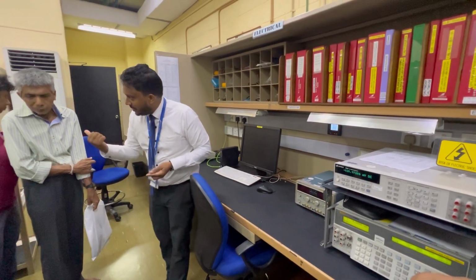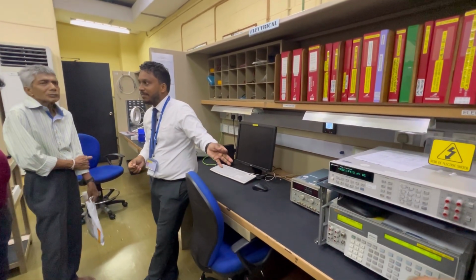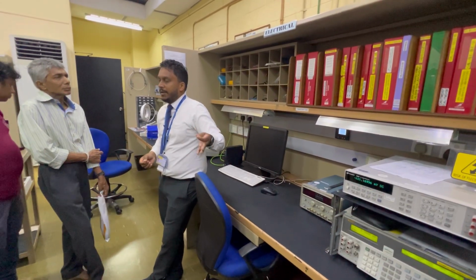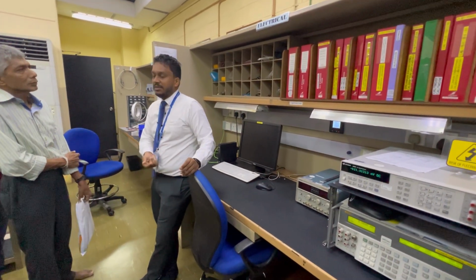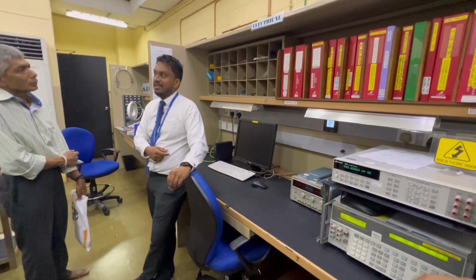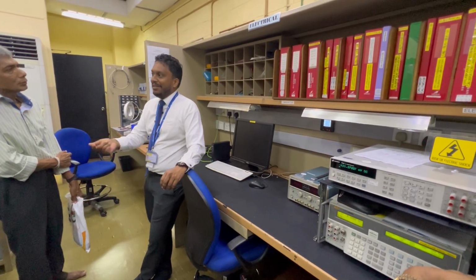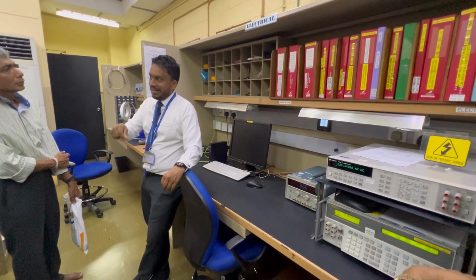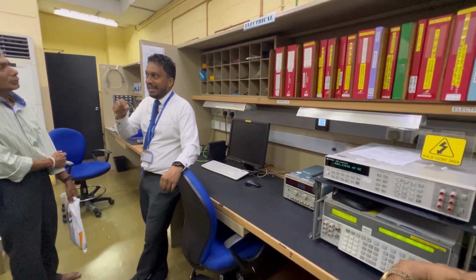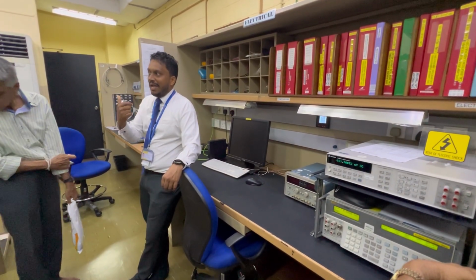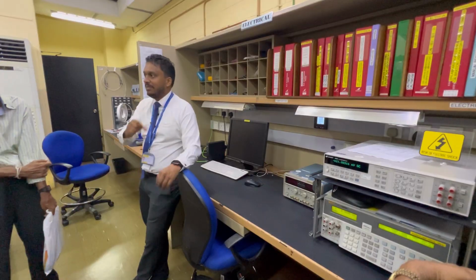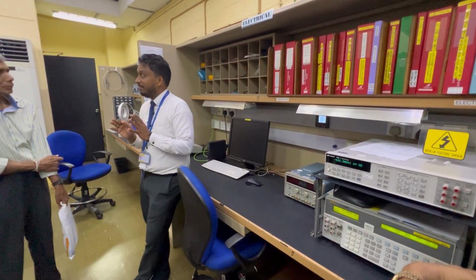But still, as you asked, suppose this deviates, or suppose I get it calibrated today, and within 3 months this happened. Suppose my calibration frequency is 5 years, 60 months, and it happened within 3 or 6 months. So from the day that I had drifted, every measurement that I do, maybe the error is from my reference, which is a big problem.